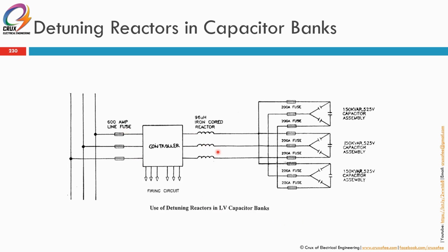So this is a detuning reactor. This detuning reactor will offset, or detune, the frequency of this capacitor bank. How much it is detuned is given by 1 over square root of LC, which is the detune frequency, or the resonant frequency of this capacitor bank. You must make sure the resonant frequency of the capacitor bank, 1 over square root LC, differs from the harmonic frequency of that system. If it's high on the 5th and 7th, make sure you detune it to the 4th harmonic or 8th harmonic, something like that. Okay.